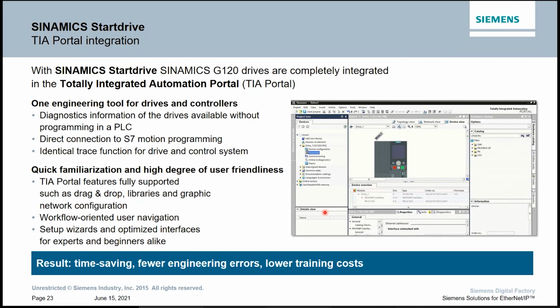First and foremost, TIA Portal is something we use from a Siemens standpoint to parameterize and program our PLC system. We also use it for our drives, so everything's integrated into one software. From a drive standpoint, commissioning and parameterization are very easy to read, with graphical representations, and then on another tab you quickly click over.